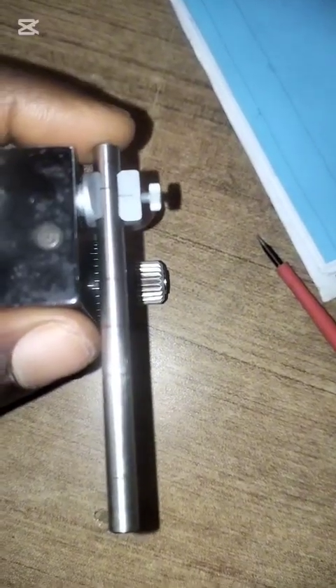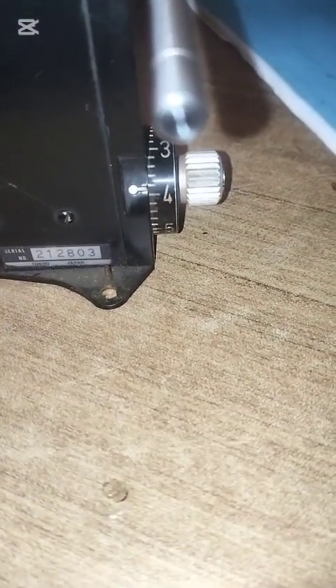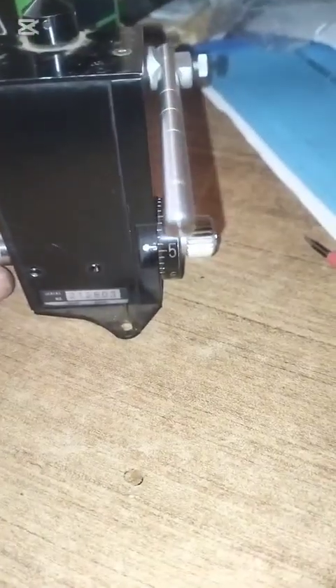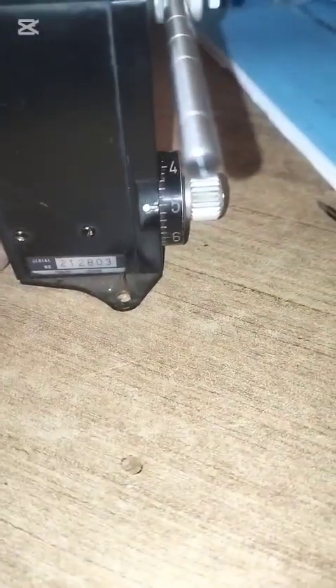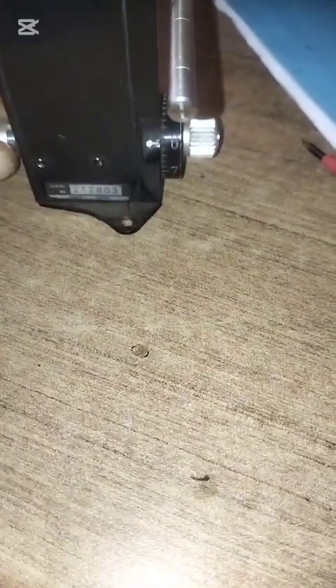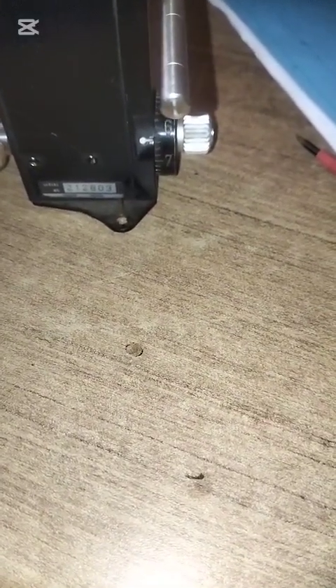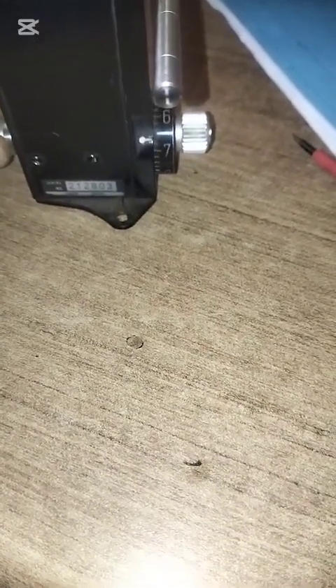So when you move it to 60 millimeter mercury, it means it has to shake only when it gets to 60. Now it's stopped, so we have to free that groove. At 60, we're supposed to get a shake of the Goldmann stick, but because it's stopped, we can't really get that shake. I'm having an error margin at almost 70.